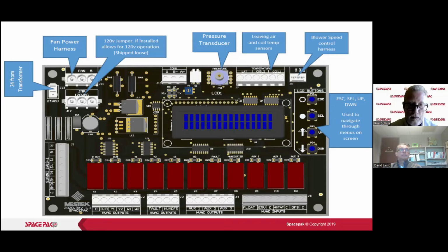electric heat. All right, so I'm gonna go off a little bit of a tangent here, and I'll try to do it quickly. There's a new board being made right now. Okay, we're up to version 4. There's a version 5 board being made now through input from the field, including my input when I put my heat pump in. There were a couple things that they're changing. But one thing I want to point out is that when we make it to that DFS, the electric heat is actually brought on through W2. So you want to use for your electric heat, W2 down here.